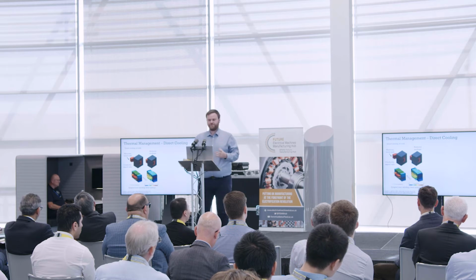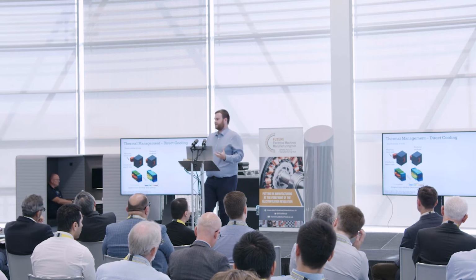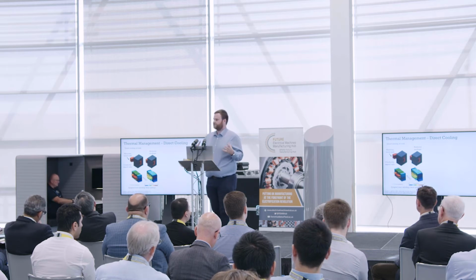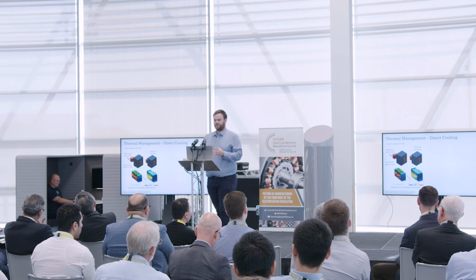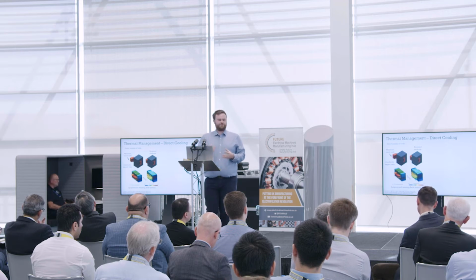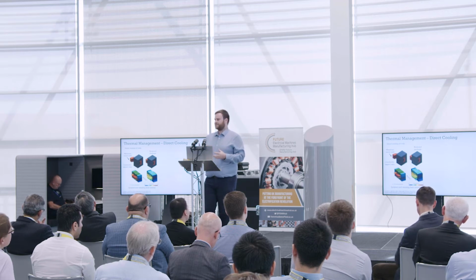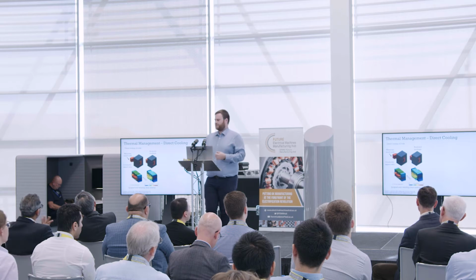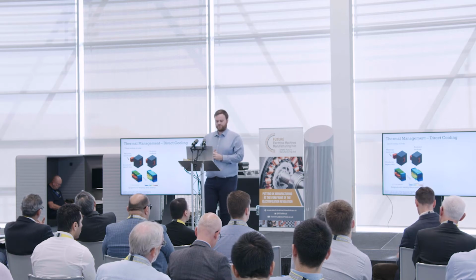The first part of this is recognizing that one of the advantages of additive is that we can reduce the overall package of the conductor. This is principally through reducing the size of the end windings, because we no longer have to worry about minimum bend radii or the insulation of the conductor itself.